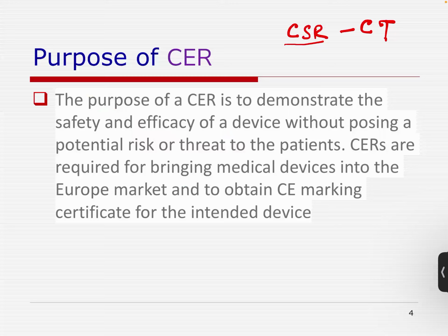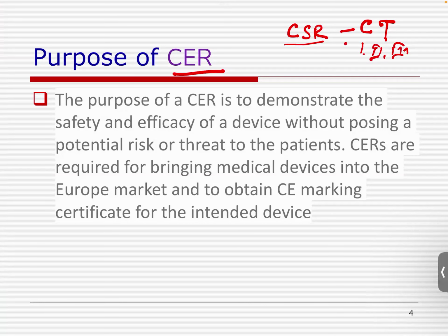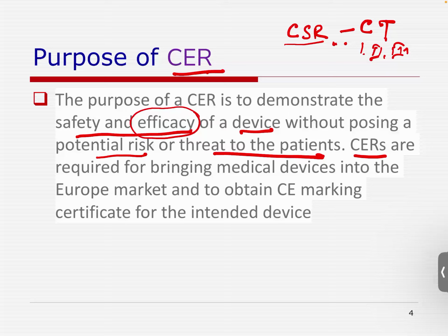Like you have done phase 1, 2, 3, all that, we do after the clinical trial. The only difference is that it is for vaccines and drugs, while this is for devices. It demonstrates the safety and efficacy of a device, where efficacy may be replaced with performance, and many times without posing potential risk and threat to a patient. Clinical evaluation reports are required for bringing a medical device into the market.